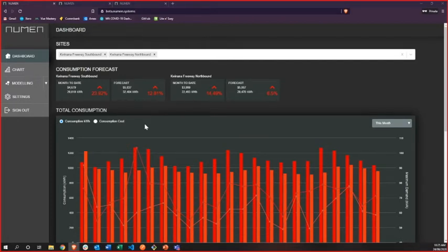By non-intrusive, I mean we simply clip those current transformers around the supply cable. With only those sensors, no vibration or other sensors on the electrical devices, we are looking to determine the state and operating conditions of these devices, to predict faults and things going wrong, and also to monitor the device as it operates, looking at its various operating modes and states.